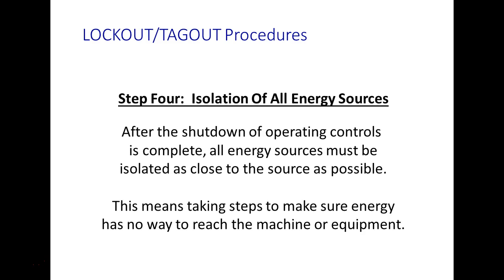Isolating all energy sources. I've shut down the operating control. All energy sources must be isolated as close to the source as possible. This means taking steps to make sure energy has no way to reach the machine or equipment. So this is where we would shut off the disconnects. We usually call them disconnects. A disconnect is not a push button, right? You understand? A disconnect is going to be something that's lockable. It is actually at the source of the energy. Everybody understand that? Now, that might be misleading. It's at the source of the energy for that device.